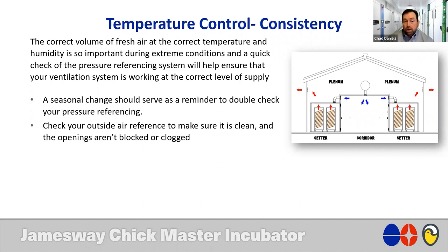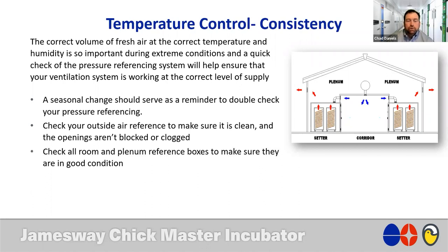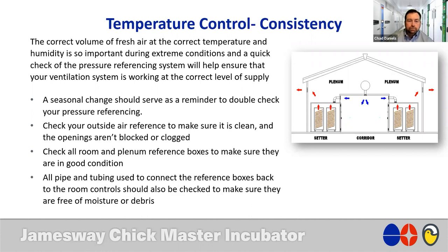Check the outside air reference to make sure it is clean and the openings aren't blocked or clogged. A lot of times we see hatcheries with pressure issues and ventilation problems, and this can be a culprit of that issue. The outside reference box has dirt buildup in it, or it's got condensation in it, and it doesn't give you a good outside air reference. Same goes for any room or plenum reference box, to make sure they're in good condition.